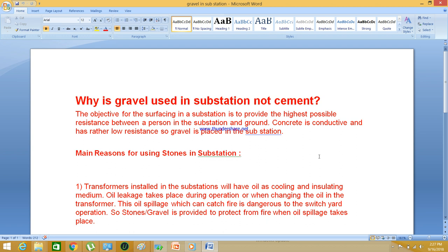There are many other advantages of using gravel in the substation. One important reason is that a transformer installed will have oil — most outdoor transformers are oil-cooled, ONAN transformers: oil natural, air natural. Oil is used for cooling purposes. When operating transformers, there may be oil spillages in the substation yard, and these oil spillages may attract fire and are hazardous.